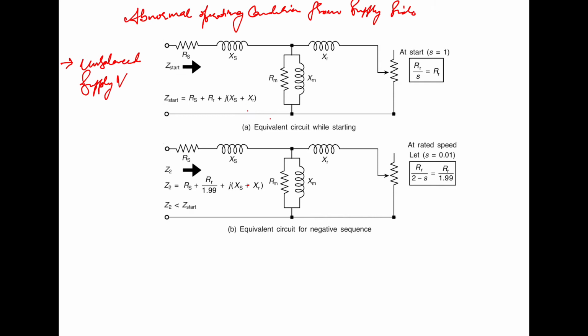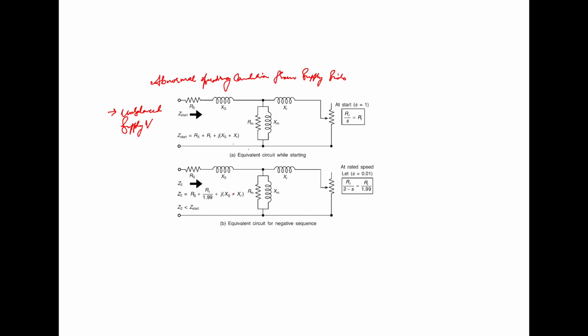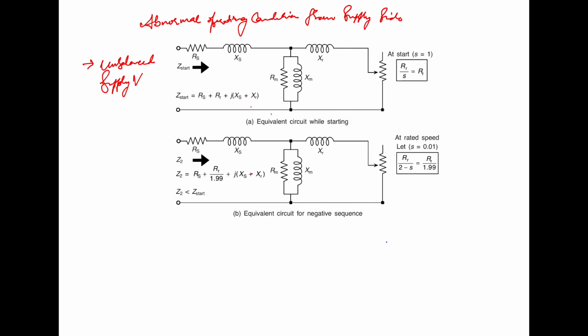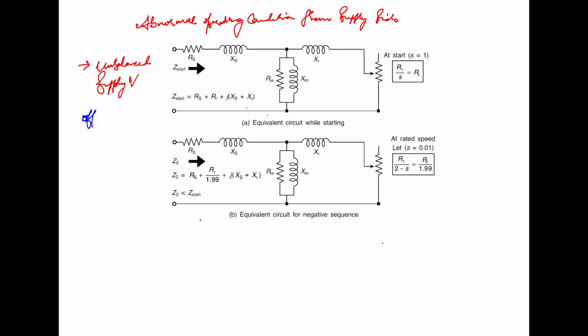Now, unbalanced supply voltage. Large induction motors are very sensitive to unbalanced supply voltage. Because of this unbalanced supply voltage, the negative sequence component comes into the picture, which is actually very troublesome, and this is because the motor offers a very small impedance to the negative sequence current component.